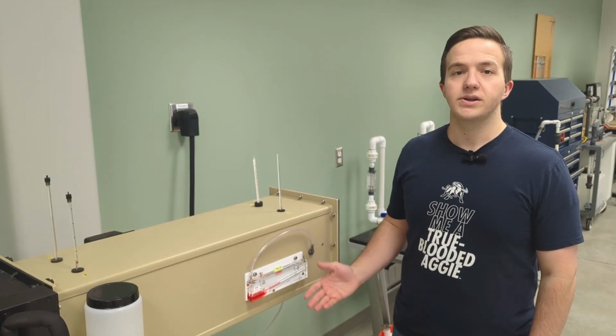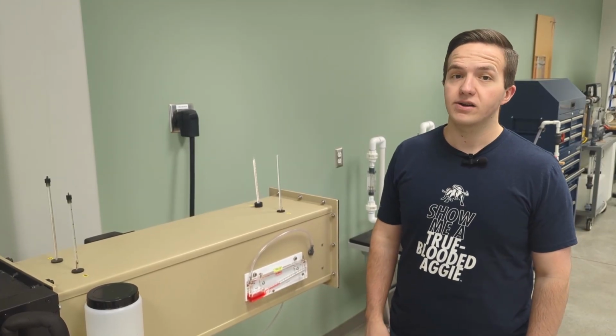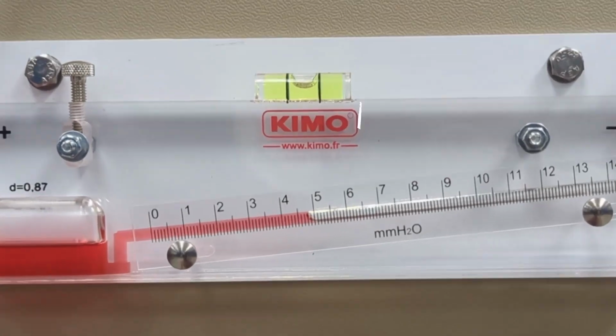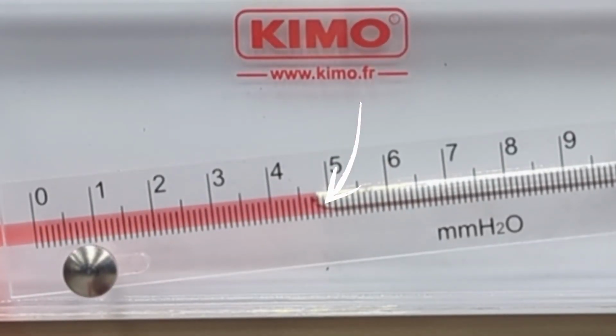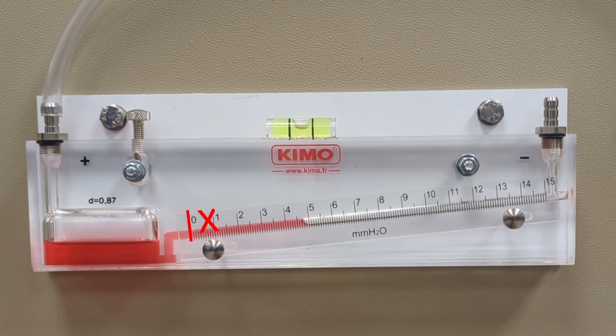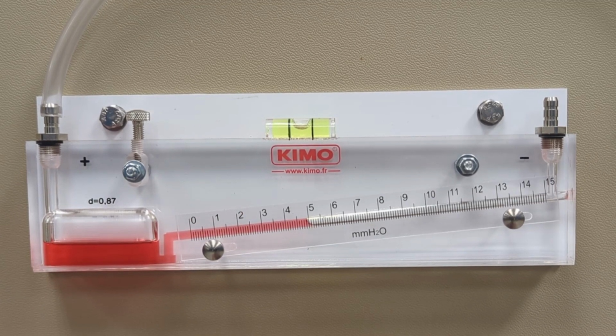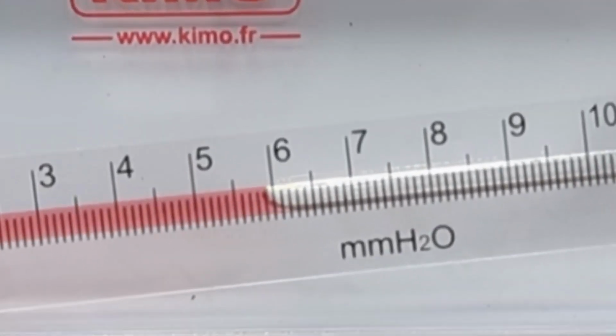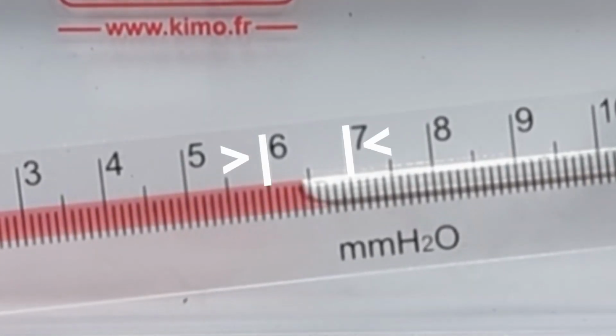The incline manometer is used to measure pressure difference and calculate airspeed within the flow. Read the pressure difference off the center of the meniscus. The manometer is generally not accurate below 4 millimeters H2O. To avoid oversaturating the end thermometers, as previously mentioned, use an airspeed that results in a pressure difference of between 6 to 7 millimeters H2O.